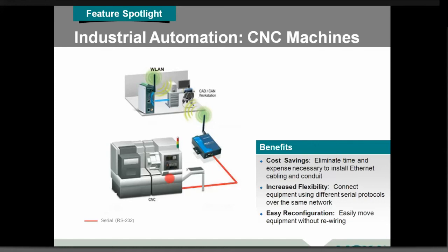And you might say, well, gosh, why don't I just drop a Cat5 cable down to the machine? And the real benefit here is what's the cost in doing that? Got to have an electrician come in, put in conduit for that. We've got to pull cable for that, bring that to a switch. We've got to make sure that that Cat5 cabling is not more than a couple hundred feet for the capabilities of that. We might have to run media converters to do fiber to the access point to do that, right? So the real value here is that cost savings.